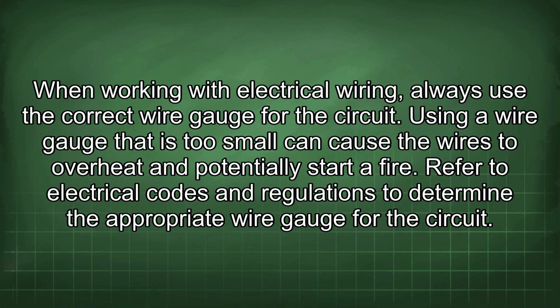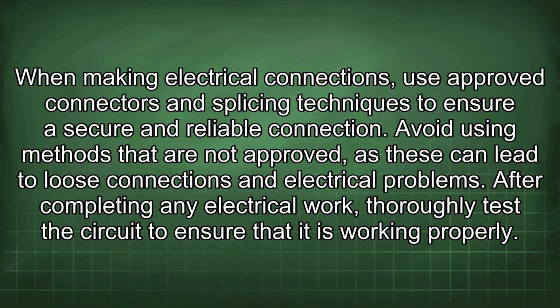When working with electrical wiring, always use the correct wire gauge for the circuit. Using a wire gauge that is too small can cause the wires to overheat and potentially start a fire. Refer to electrical codes and regulations to determine the appropriate wire gauge for the circuit. When making electrical connections, use approved connectors and splicing techniques to ensure a secure and reliable connection. Avoid using methods that are not approved, as these can lead to loose connections and electrical problems.